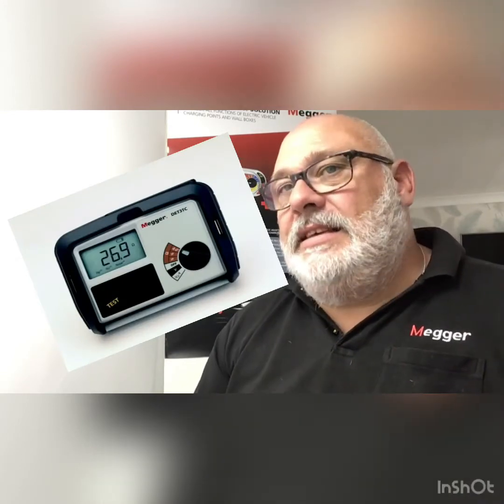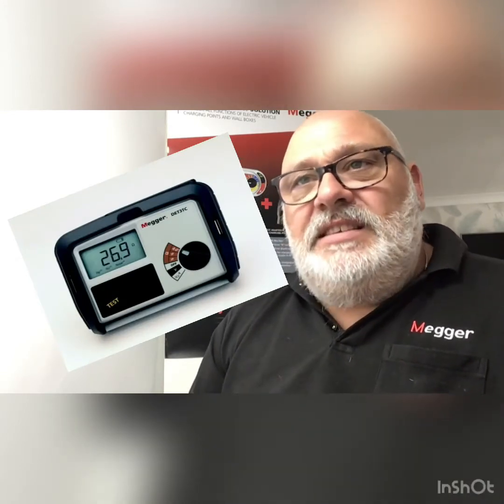Next, earth electrode testers, more commonly known as the DETs. Earth testers are used to confirm the resistivity of the earth spike or the electrode. These are often installed when no earth connection is provided with the supply cable. The 3 and more accurate 4-wire method of the test is normally used, with one connection made to the earth electrode being tested.